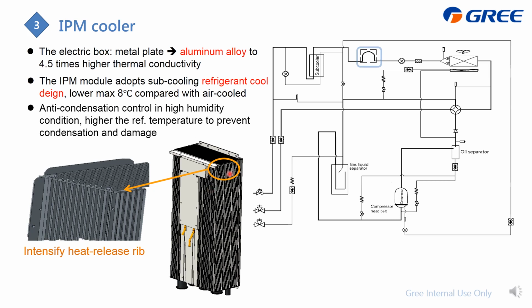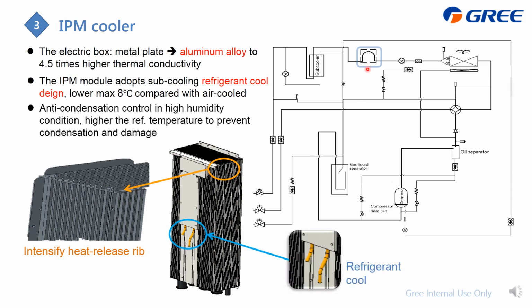And for the IPM cooler, you may have a worry that on the surface of it, if in a high humidity condition, we will get condensing water, and the condensed water, if it generates at the IPM, it will also be very easy to make it to be damaged. And for this one, we already consider about it, and also we have the solution, which is to higher the temperature of this refrigerant to avoid the refrigerant lower than the dew point, which this will not generate the condensing water.